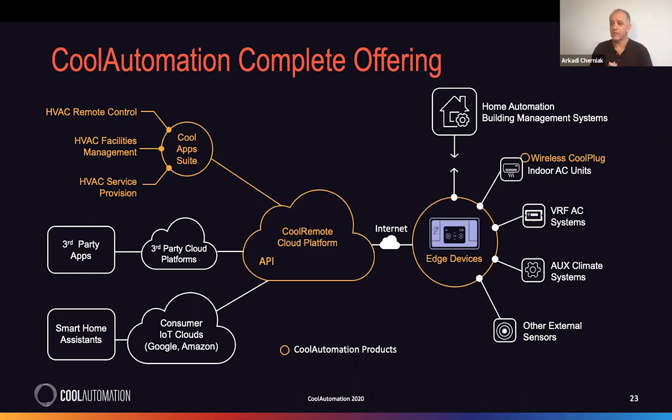A single CoolMaster net can support 2 or even more brands. Capacity-wise, it can reach up to 256 indoor units. This is huge. Brand-wise, one port is configured for Samsung, the other one will be configured for Daikin. And then both floors are consolidated in controls into one set of controls. So that's number one hybrid.